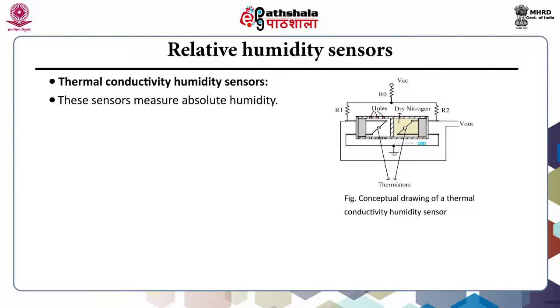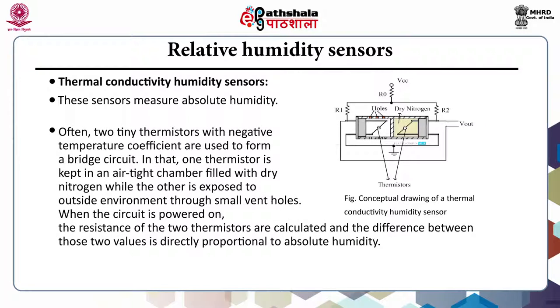The third type is thermal conductivity humidity sensors. These sensors measure absolute humidity instead of relative humidity. In this type, two tiny thermistors with negative temperature coefficients are used to form a bridge circuit. One thermistor is kept in an airtight chamber filled with dry nitrogen while the other is exposed to the outside environment through small vent holes. When the circuit is powered on, the resistance of the two thermistors is calculated and the difference between those two values is directly proportional to absolute humidity.